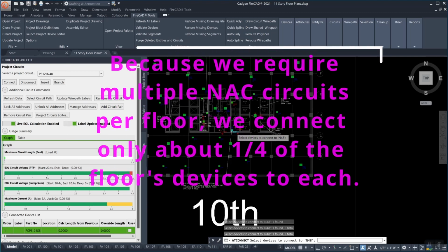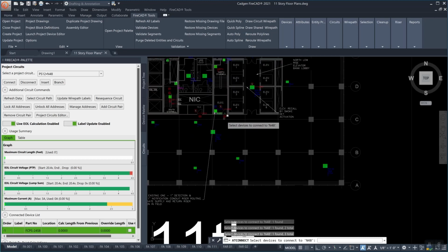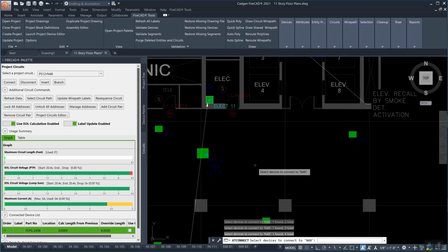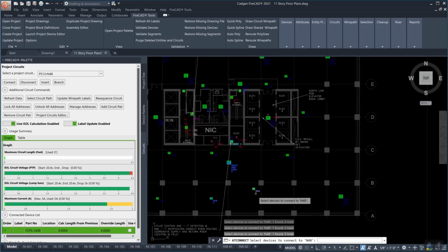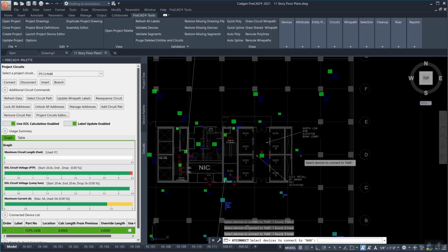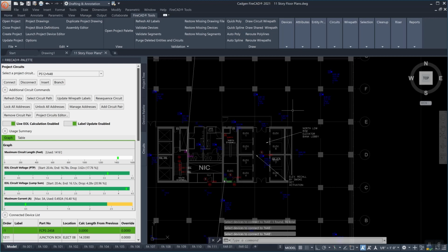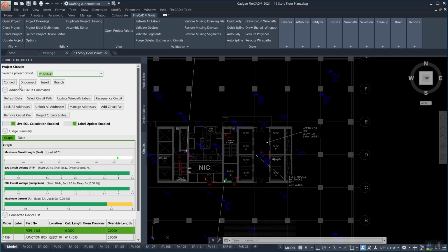And because we require multiple NAC circuits on each of these floors, we're going to only connect about 1/4 of the NAC devices onto each of the NAC circuits. That's our first quarter, and then NAC circuit 47.